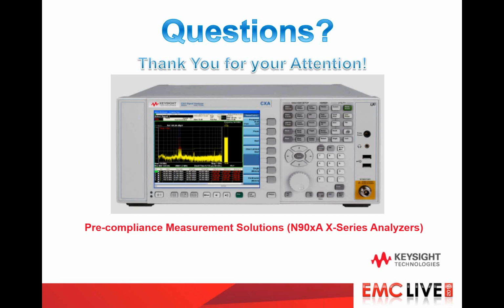One more. How important is it to calibrate antennas used for radiated emission testing? It's important to have the antenna factors in there. So you're not calibrating the antennas, you're purchasing antennas, and there's several very good suppliers here in the U.S. that make antennas. TDK, ETS Lindgren, they make very good antennas. They all have antenna factors built around their antennas, and you just need to be sure to put that in when you're doing your actual measurements. Because again, if you don't have the antenna factors in there, you may think it passes, you take it into a full compliance house and you have a failure. Great. Critical to put those in.